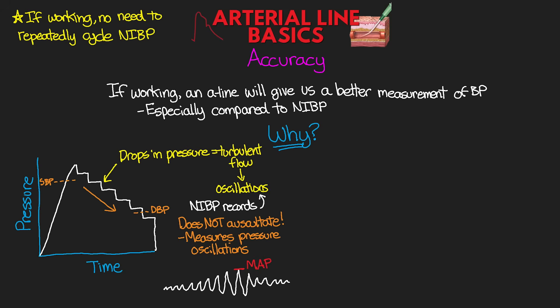The maximum amplitude is going to be our patient's mean arterial pressure, or their MAP, and this is actually generally relatively accurate. As the amplitude drops back down, when it reaches 80% of what the maximum is, this is going to be our patient's diastolic pressure — less accurate than the MAP, but still relatively accurate. For the systolic, though, this is where we run into accuracy issues. We don't have a good way to actually determine this. There are two schools of thought for different manufacturers: first, they can calculate the systolic blood pressure from the MAP and the diastolic blood pressure — not the greatest for a measure of true systolic. Second, we know that systolic blood pressure occurs when the size of the oscillations are somewhere between 25 and 50% before we reach that maximum, and thus they can guess based on this knowledge. Again, not a great solution.